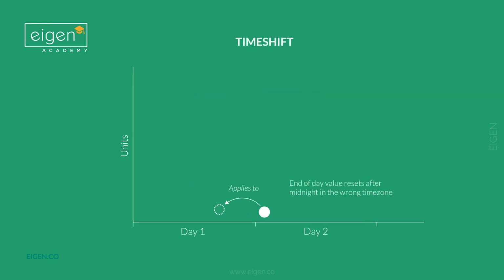And now let's look at the time shift function. So let's say we have a point entered at some point in day 2, but it actually applies to day 1. An example might be an end of day value that resets after midnight and or in the wrong time zone. We need to move it back a fixed amount. And because it's a computer generated value, it's reliable. The offset from when it should be is known, it's repeatable, and so we can apply a basic time shift to that data. That's what the time shift function allows.